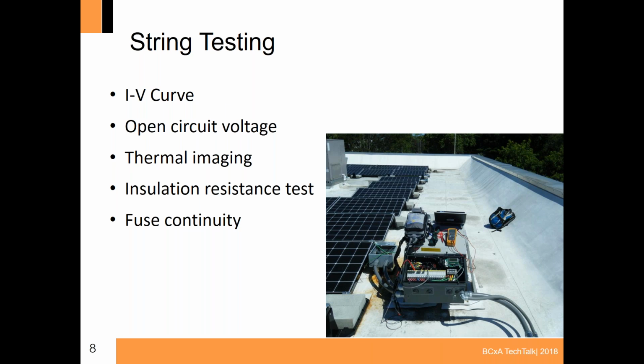But again, this is really diving into the system. As you can see on the right-hand side, there are several different tools that we would use to take these measurements. The first one, IV curve, is going to be the most common. Basically, for any given string, the IV curve trace will tell us if the strings are producing properly or not. This measures the current-voltage curves of the modules and strings and then compares the results to the module specifications. So in other words, if a module has a certain curve, we can compare these results and see very quickly, gee, we're not getting the same curve. Why is that? Is there a tree right in front of the modules, or is something not connected properly, or is there something else? So that's a nice physical way to see if it is really operating as it should be.